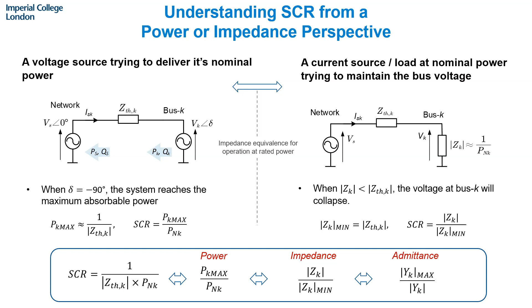It's a ratio related to power margin. From an impedance perspective, if we consider a current source load at nominal power trying to maintain the bus voltage, we know that if it's exporting its nominal power, it can be equivalent to an impedance with value 1 over its nominal power. From Ohm's law, when that impedance is smaller than the Thevenin impedance, the voltage at the terminal will collapse. So the Thevenin impedance is actually the minimum allowed impedance you can connect to that bus, meaning short circuit ratio is also an impedance margin ratio from this perspective.